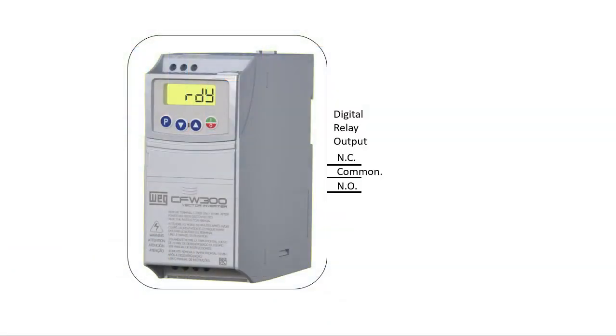The Digital Relay output on the WEG CFW300 variable frequency drive defaults to sending out a no fault status — that is, it's active as long as there's no fault.